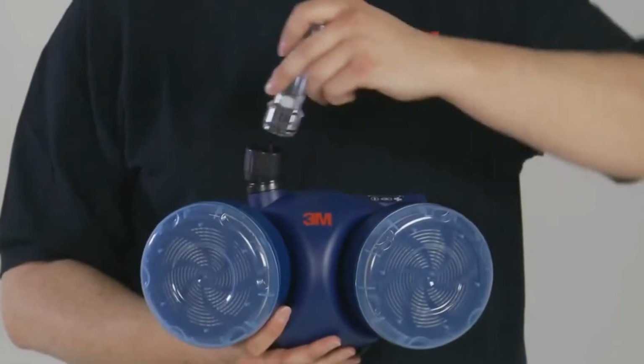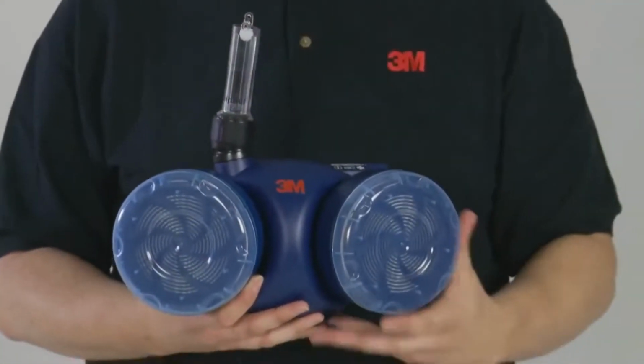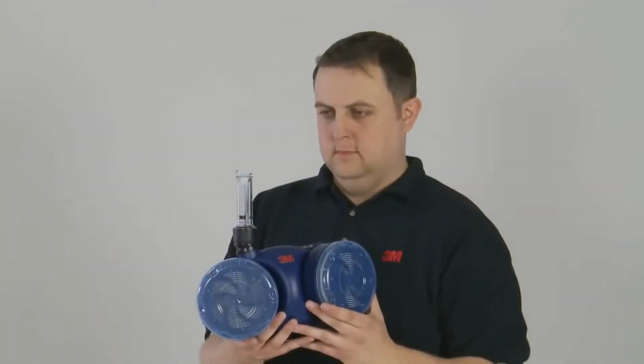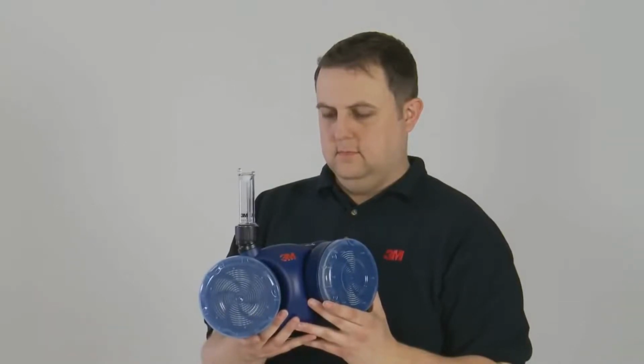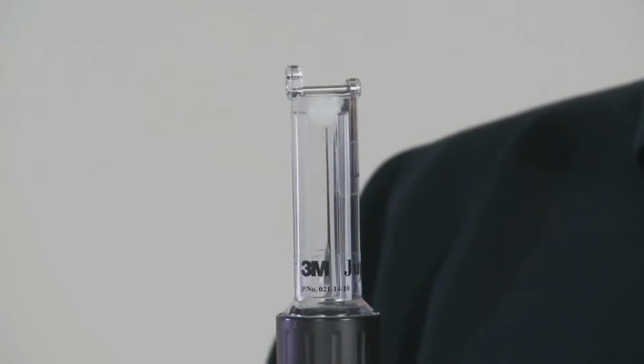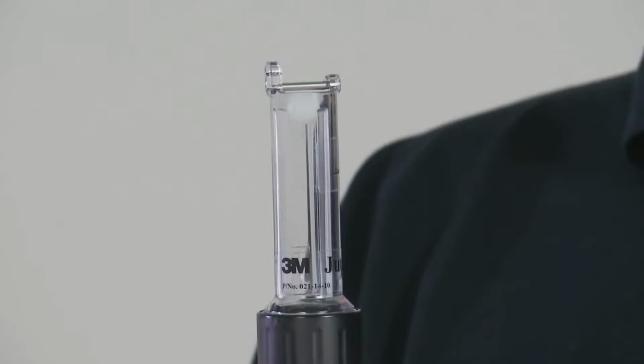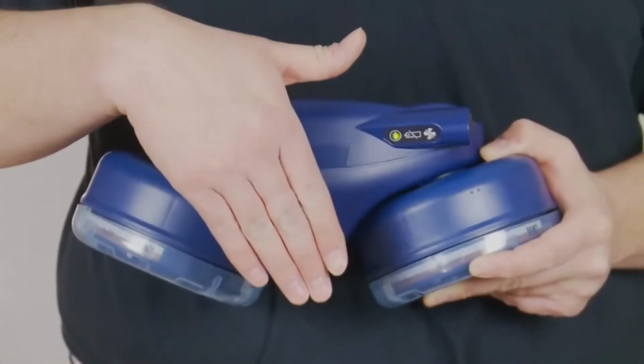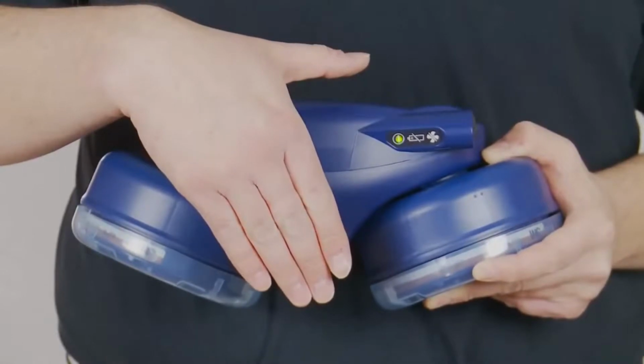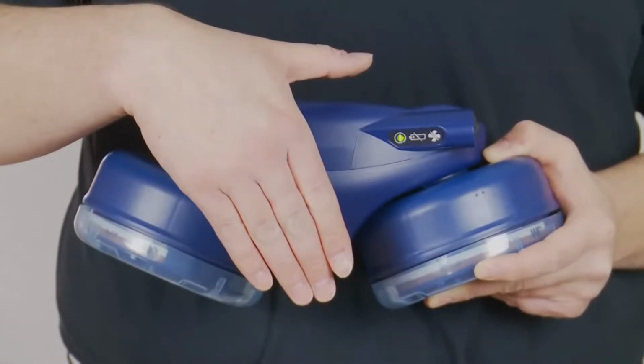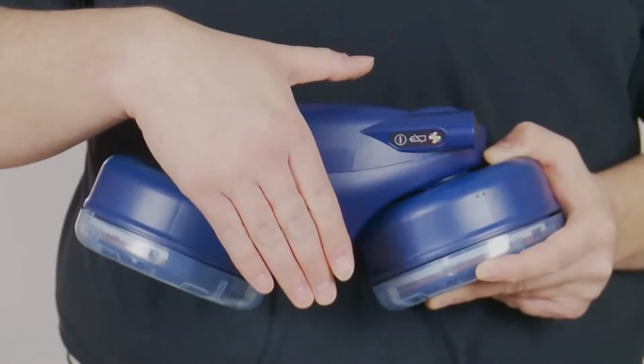Check the airflow by using the provided airflow indicator. Holding the unit with the airflow indicator upright, check that the bottom of the ball rests at or above the minimum flow mark. Check that the in-use alarms are working by placing a hand over the outlet of the turbo. The alarm should sound and the fan LED should flash.